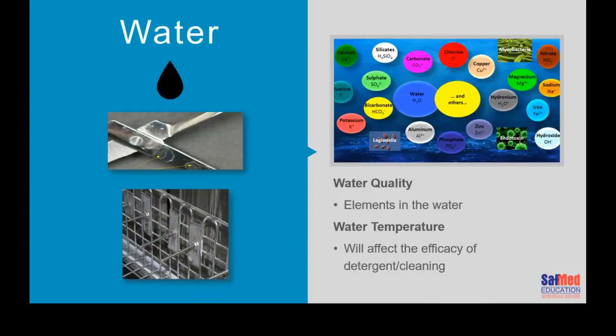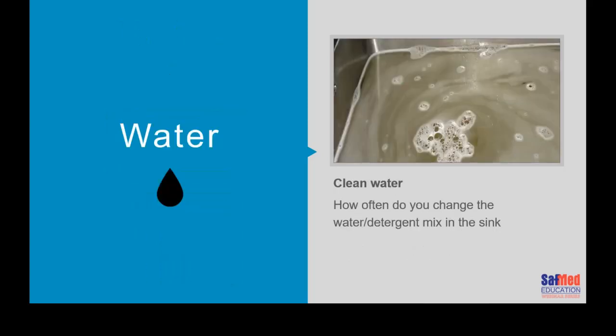Another important aspect about water is the water quality, or the quality of the water itself, and what water contains, because naturally there are a variety of elements and minerals in water, including, of course, potentially microorganisms, copper, chlorine, carbonate, silicates, sulfates. They all exist in standard tap water. If you have a look at the image on the left, you'll see lots of white spots on instruments, white spots on the inside of an automated washer disinfector. And that's all from minerals in water. That's why the international guidelines recommend that the final rinse phase of instrument cleaning should actually be with demineralized water.